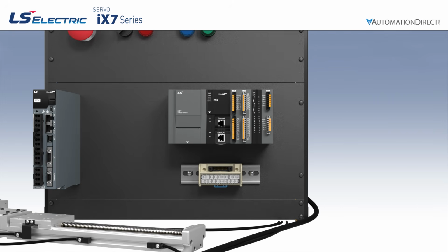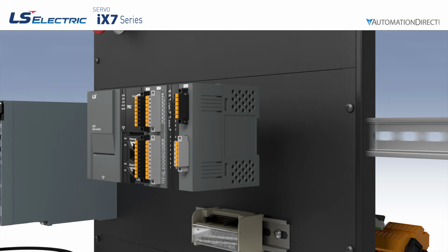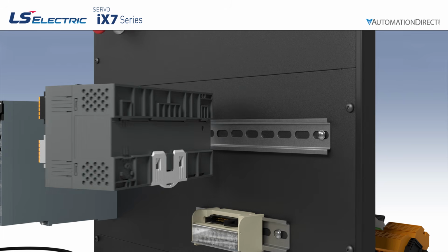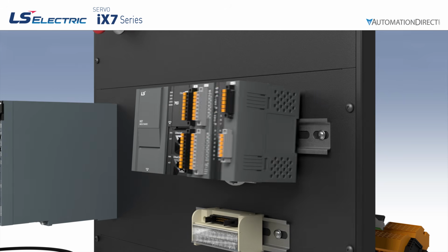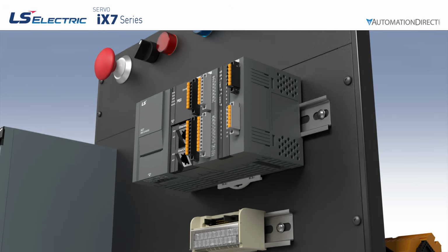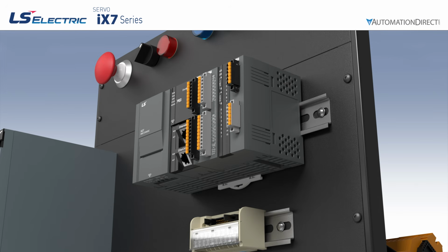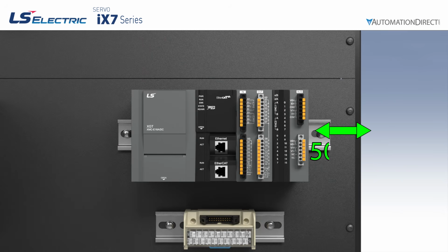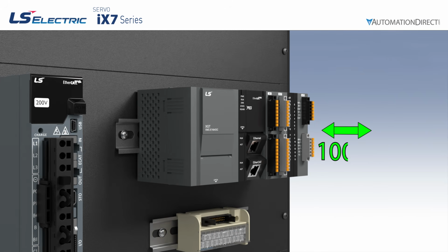Next is the XMC motion controller. This unit snaps onto a 35mm DIN rail. Pull down the bottom locking hook, set the top hook onto the top edge of the DIN rail, then rotate the unit down until it clicks. Push the bottom hook back up, securing the controller. Give it 50mm of clearance on each side, 30mm above and below, and 100mm in the front.